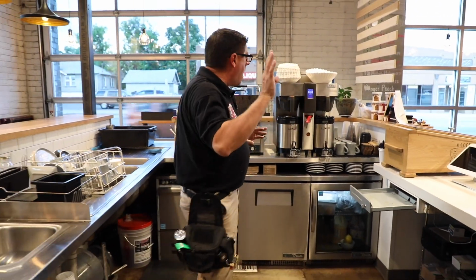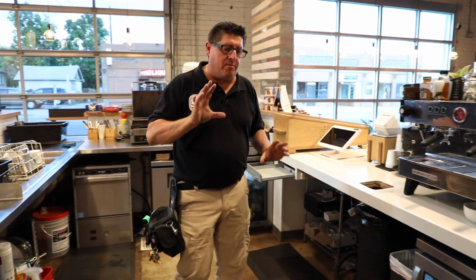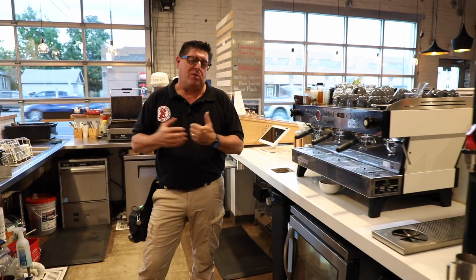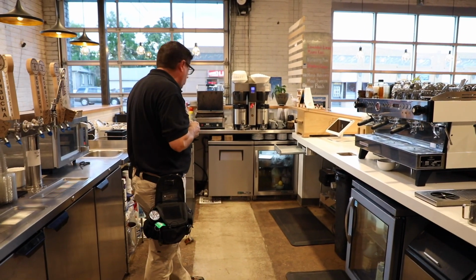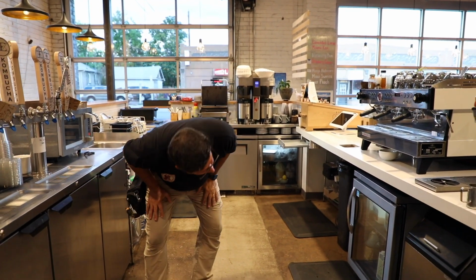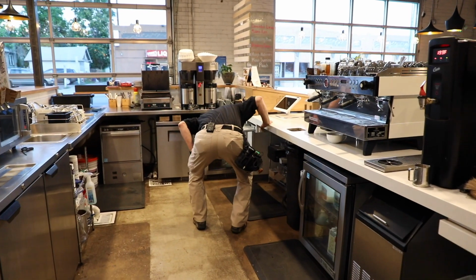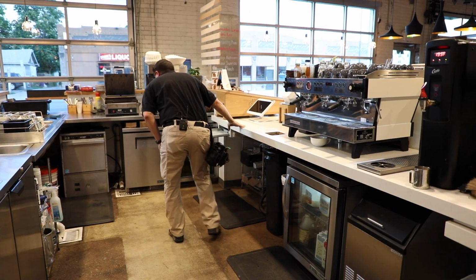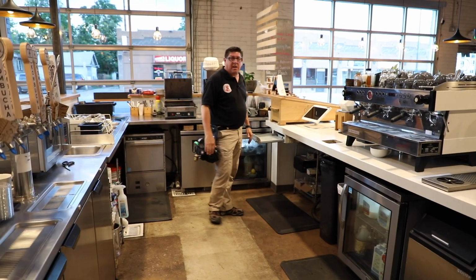I don't care about the coffee makers or the panini press. I'm just watching the drainage, and I'm just watching the installed systems. And then lastly, I would want to make sure that wherever I see electricity, if I can get to it, they are ground faulted. And in this particular case, I don't see ground faulting.